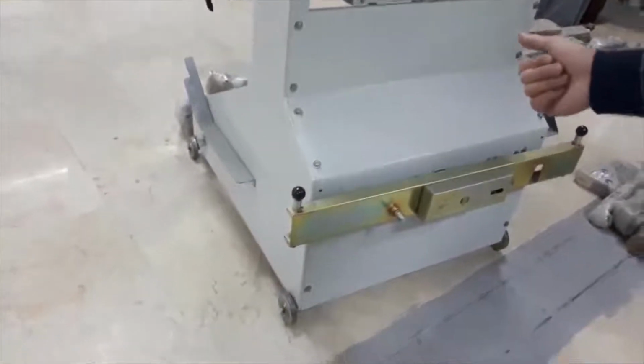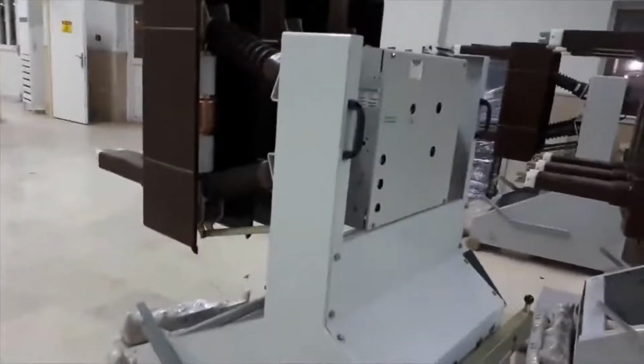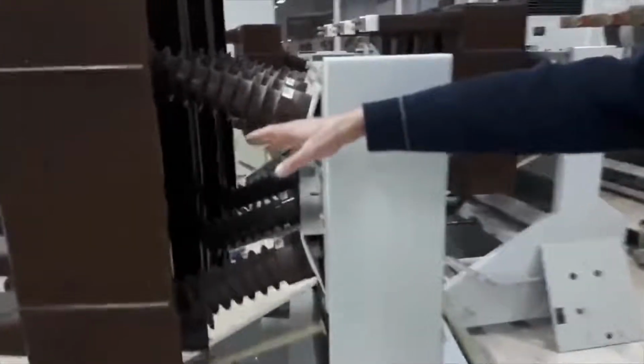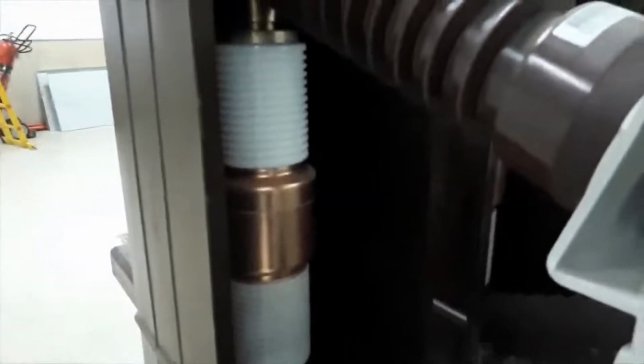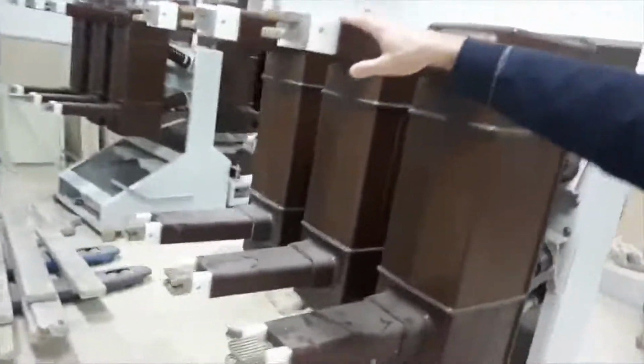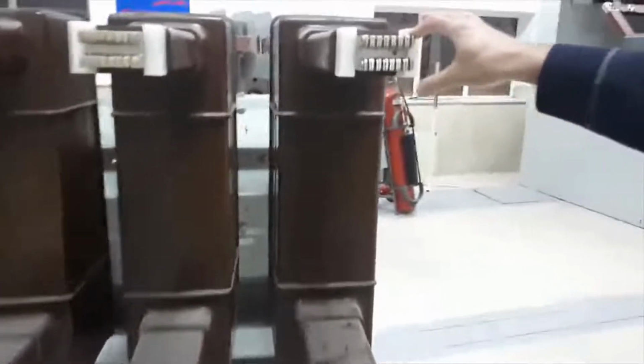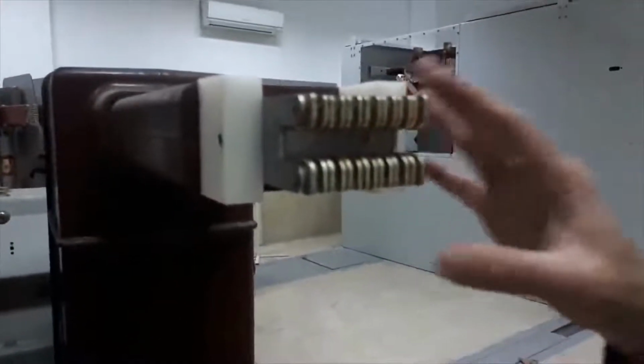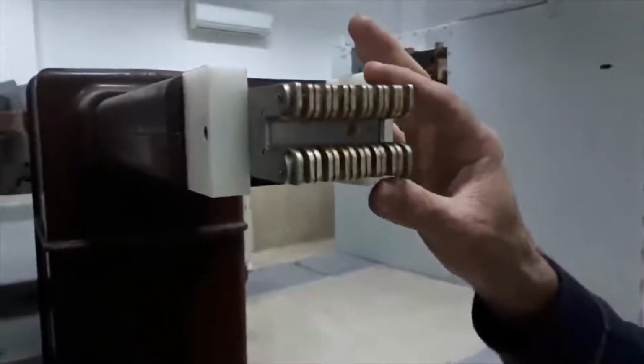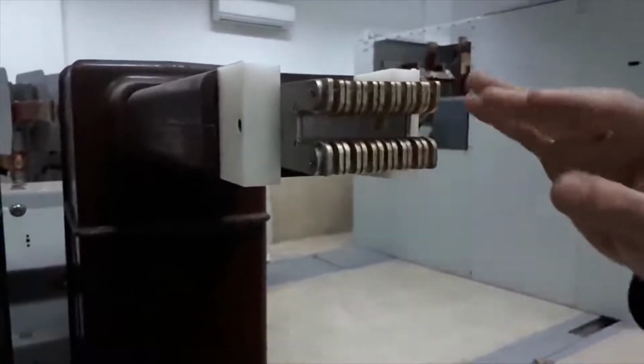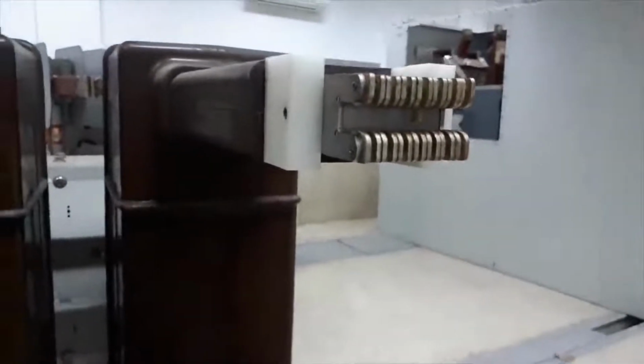Yes, here you can see the 33 kV trolley with the breaker mounted on it. Here you also see the 33 kV vacuum interrupter. The breaker is of vacuum type and its contacts are located inside this vacuum interrupter and are opened and closed. And in this section you can see the power contacts of the breaker, which, when the breaker is racked in and mounted inside the switchgear, they connect to the bus bar and the current enters through it and exits from here and is given to the output feeder.